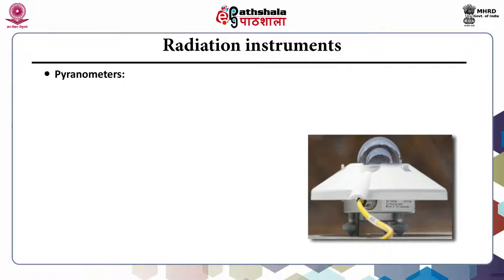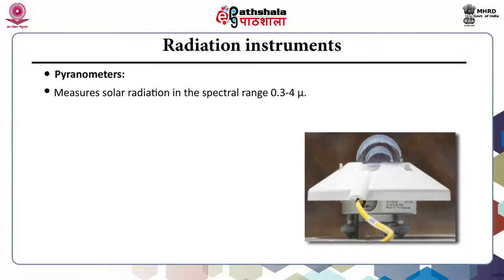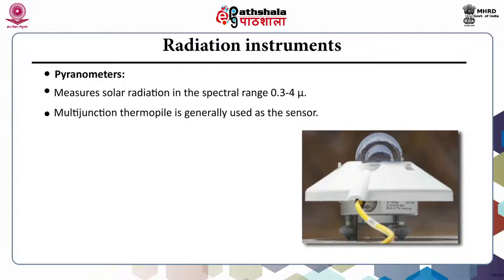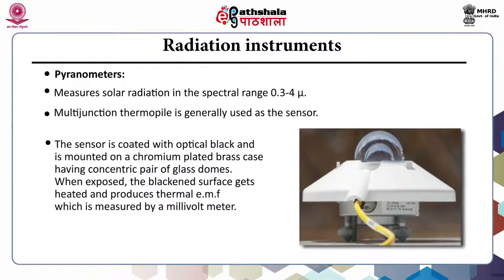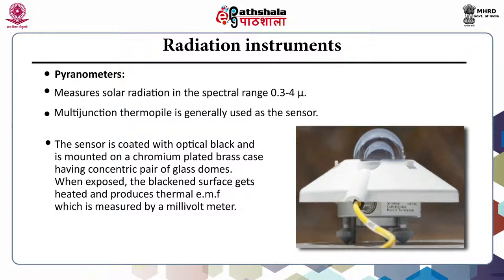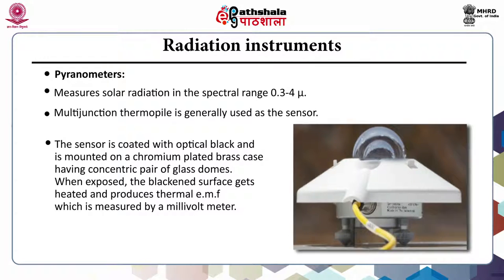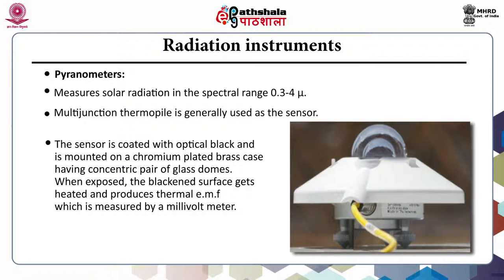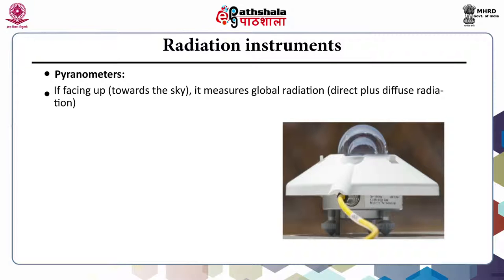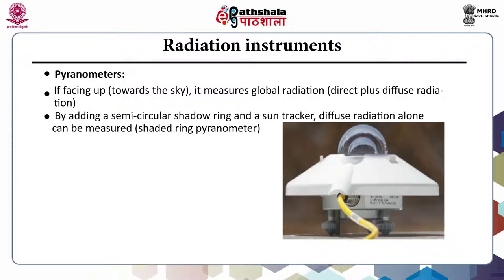The next radiation instrument is the pyranometer. It measures solar radiation in the spectral range 0.3 to 4 microns, also called short wave solar radiation. A multi-junction thermopile is generally used as sensor, coated with optical black and mounted on a chromium-plated brass case having a concentric pair of glass domes. When exposed, the blackened surface gets heated and produces thermal electromotive force, measured by a millivolt meter. If a pyranometer faces up towards the sky, it measures global radiation — the combination of direct plus diffuse radiation. One variant is the shaded ring pyranometer, in which a semicircular shadow ring obstructs the direct beam so that only diffuse radiation reaches the sensor.